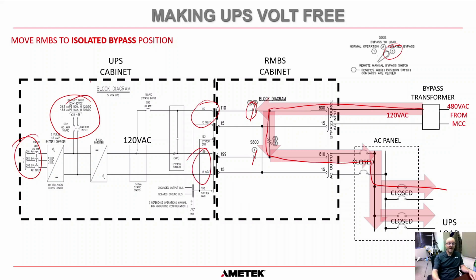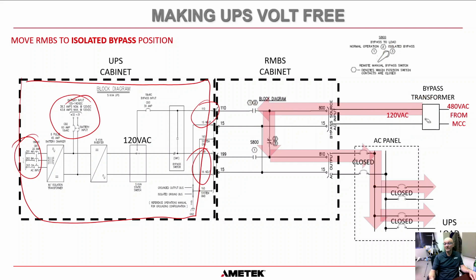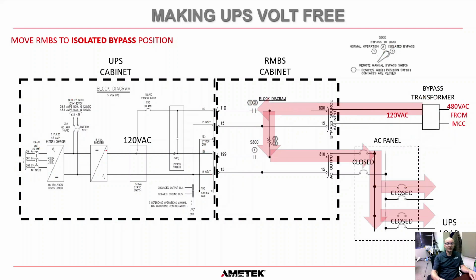And in truth, you could actually completely remove this UPS and install another UPS. It could be a different manufacturer, or the same manufacturer with a different model, whatever. You could do that while the load circuits are maintained by your bypass. You'll never lose power. That just shows you the flexibility that having an RMBS gives you. It allows you to do complete maintenance. You can replace the inverter bridge, all the capacitors and fans in the charger, and replace control boards, all very, very safely because there is now no power in this UPS whatsoever.